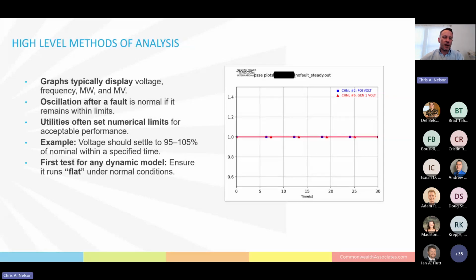Sometimes if there's a fault, it's normal for it to oscillate, but like I said, it needs to settle back down. Some utilities have specific limits for what that looks like. Some utilities are more, it looks good, it's probably good. It really depends on what the utility is, but the main point I wanted to make here is that they call it running flat. If there's no problem with the system, the voltage needs to be a flat line and preferably near 1 per unit too.